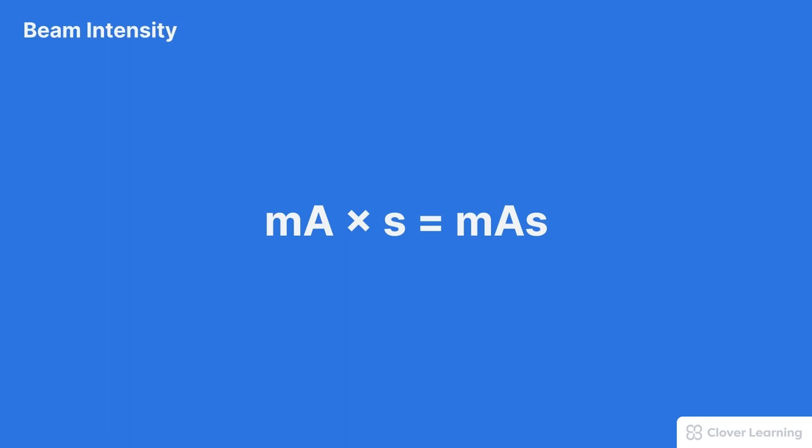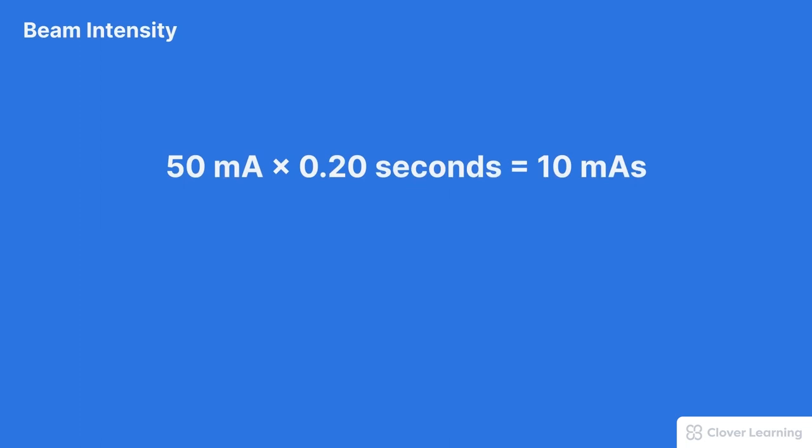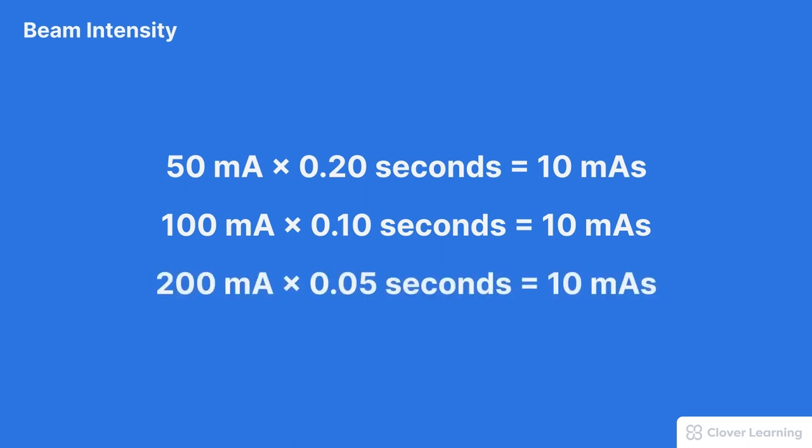There's a reciprocal relationship between MA and time. This means that multiple MA and exposure time settings result in the same total mAs and therefore the same total beam intensity. For example, 50 MA times 0.20 seconds equals 10 mAs. But 100 MA times 0.10 seconds also equals 10 mAs. And finally, 200 MA times 0.05 seconds still equals 10 mAs.